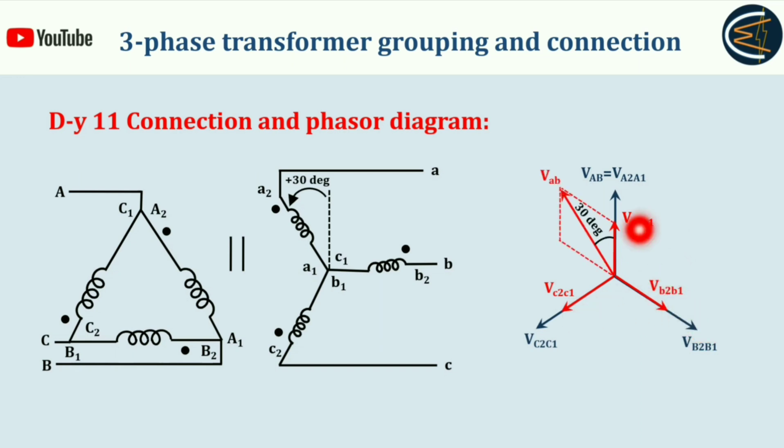The corresponding line voltage V small ab will be this. This is the resultant, and as you can see, V small ab is leading by 30 degrees with respect to V capital AB.